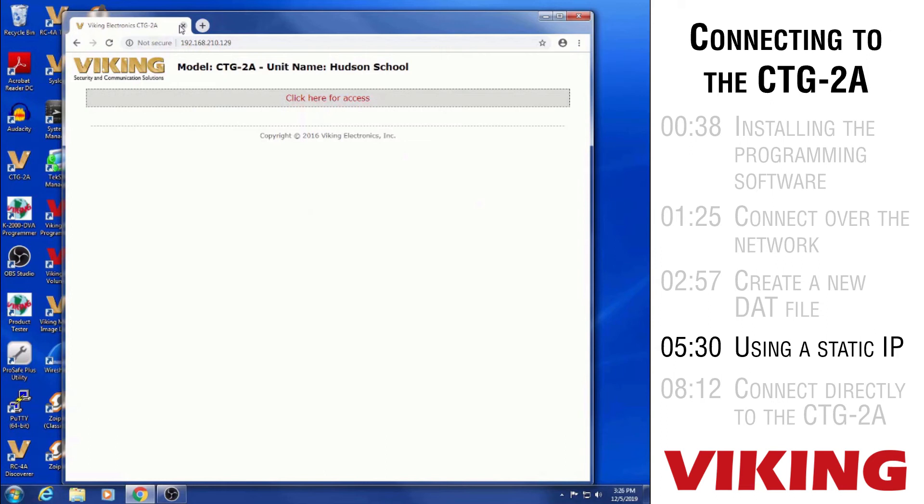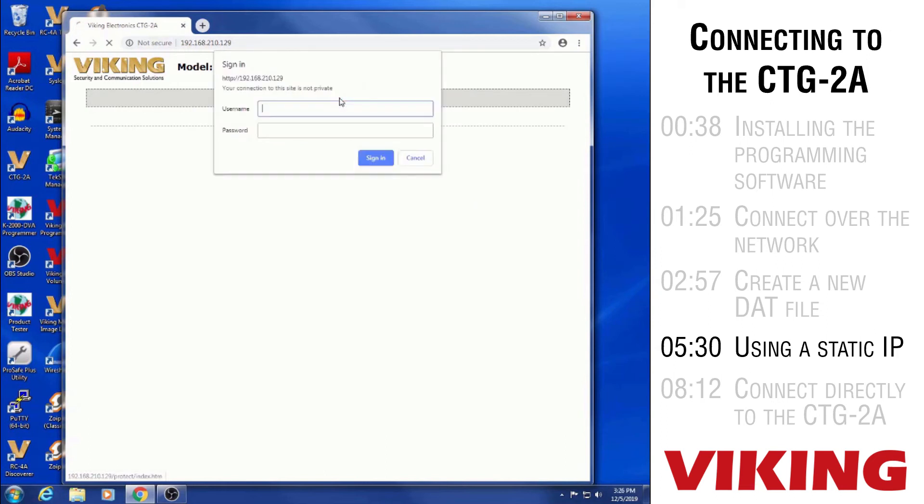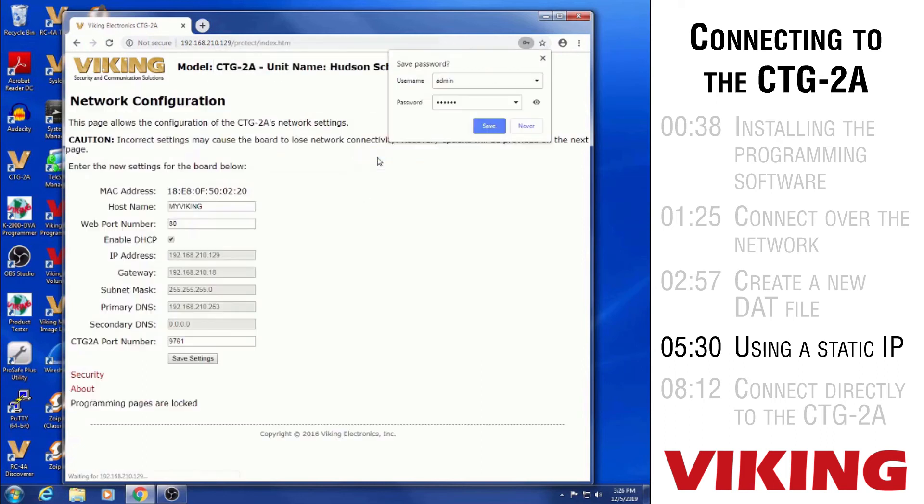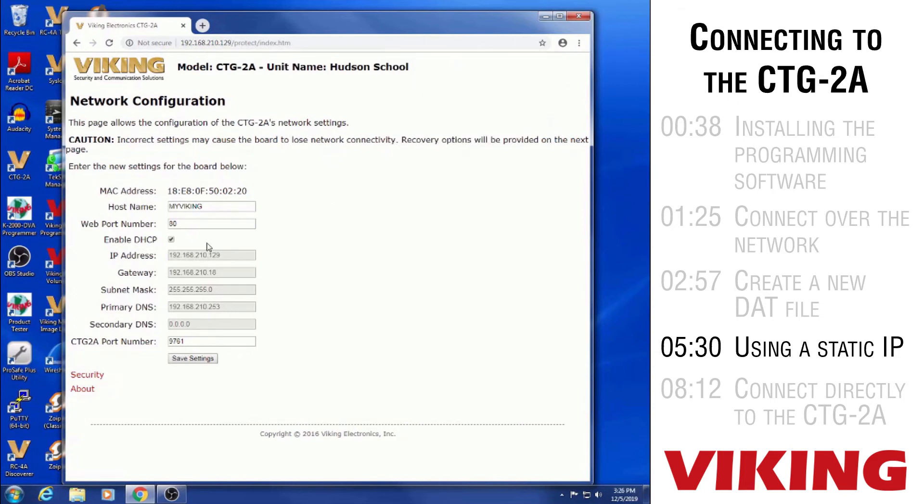See I put that into the browser using Chrome as the browser. It's showing that I'm connecting to the CTG-2A. It's asking me for a username and a password which by default the username is admin and the password is viking in lowercase. So I put in the username password and then takes me to that network configuration web page that the CTG-2A is producing.